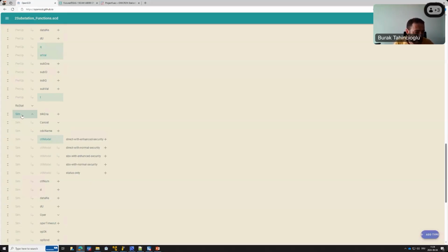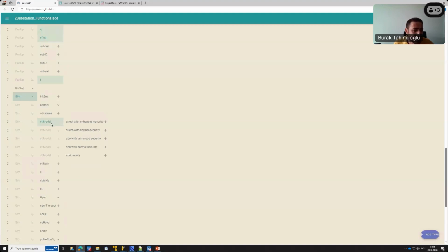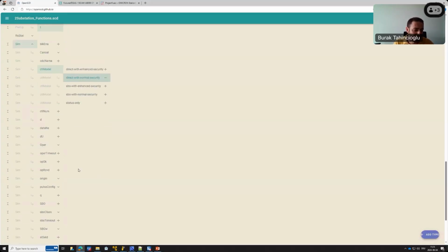Then we click Sim. You may know Sim is a controllable object, and each controllable object in the standard always comes with a control model. You can pre-select which model you want — for instance, direct with normal security only, not select-before-operate or the other possibilities. So we limit it to direct with normal security only, and don't select the other options.